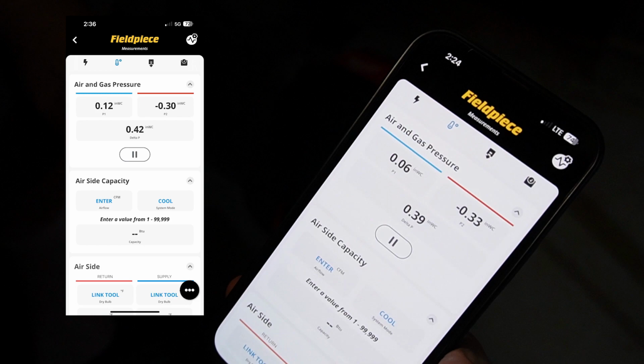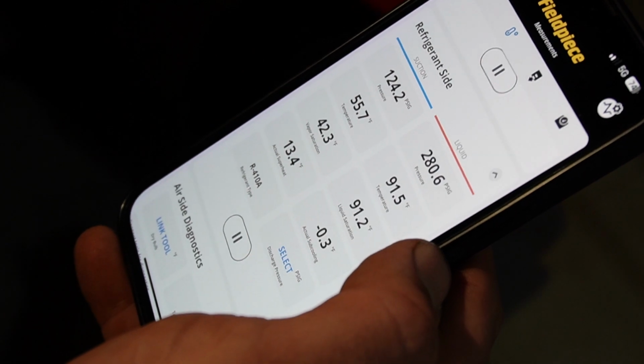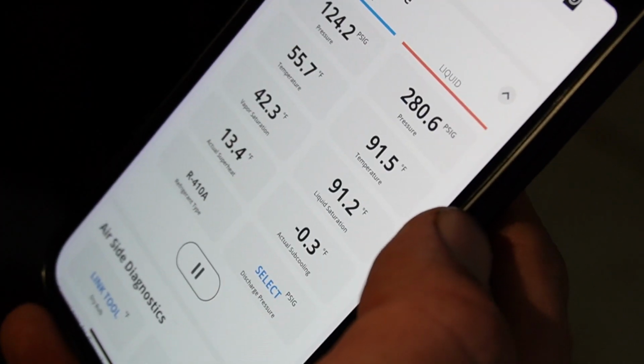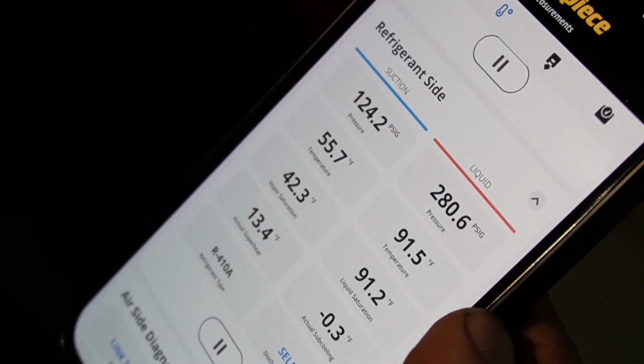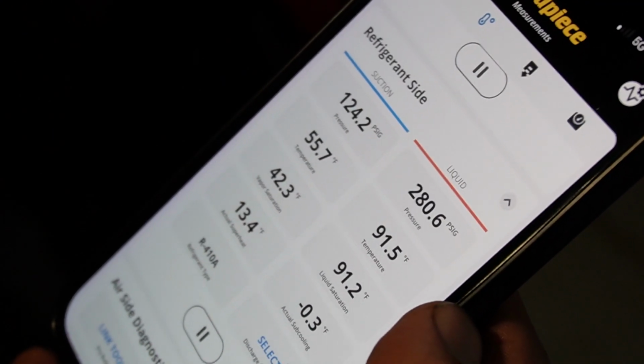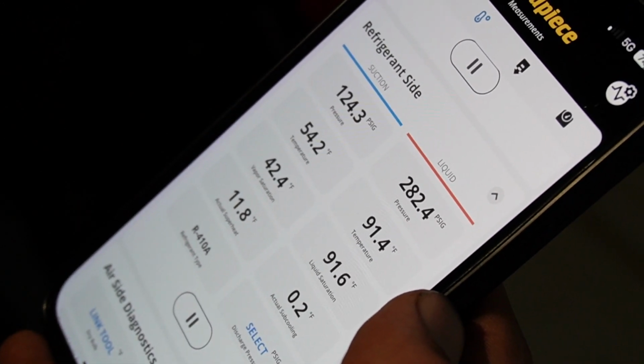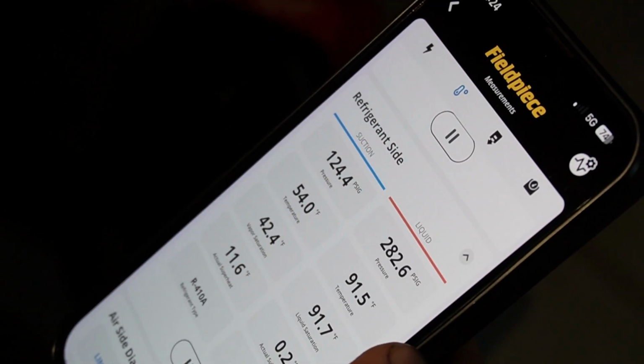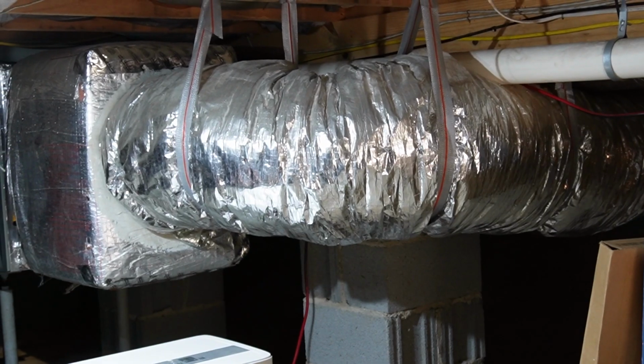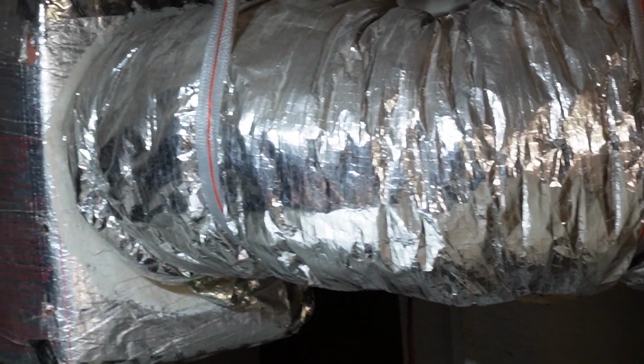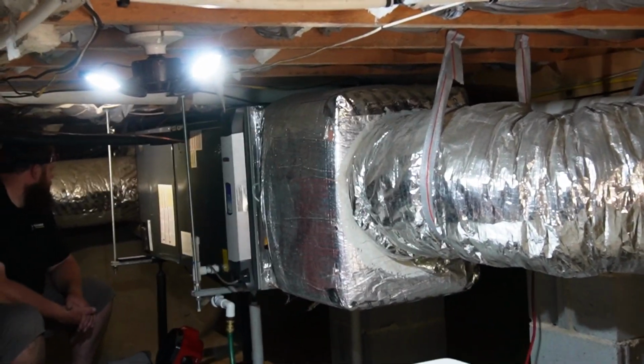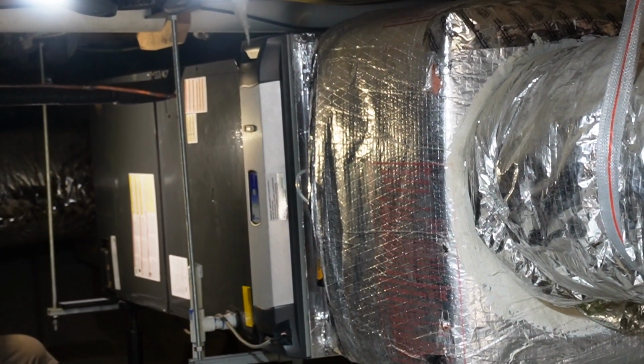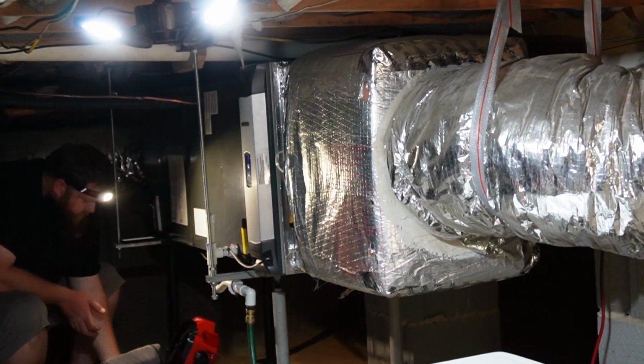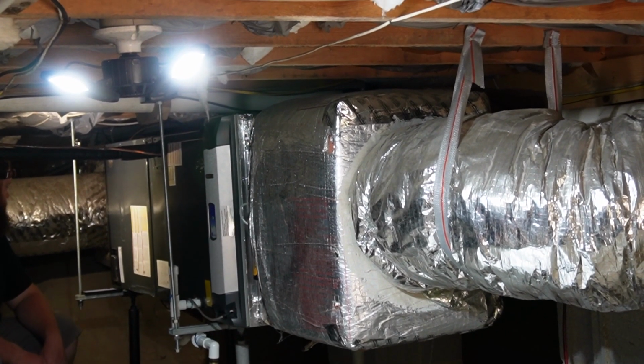There we go. Is that outdoor already? Yep, so we'll check the outdoor, but that's our readings from the crawl. We're probably 40 feet away from the outdoor unit. It's a TXV system, obviously, with it being 18 SEER. There's another return on the other side, and yeah, we were at 0.4 before the filter. Looking good on the static side.